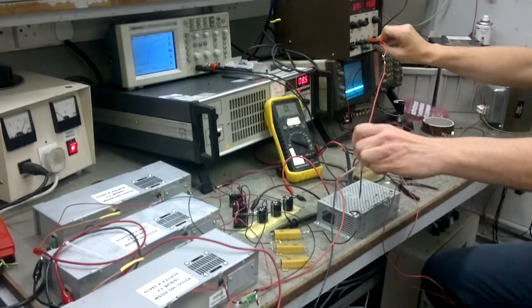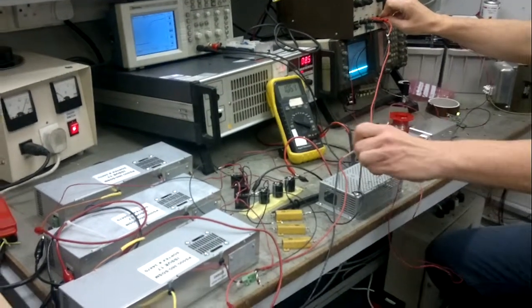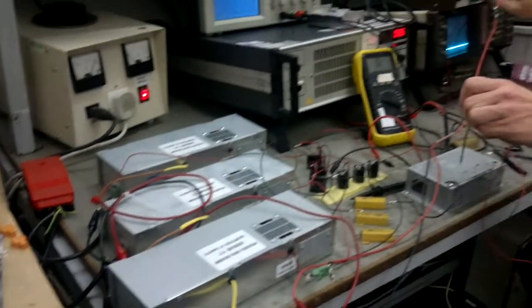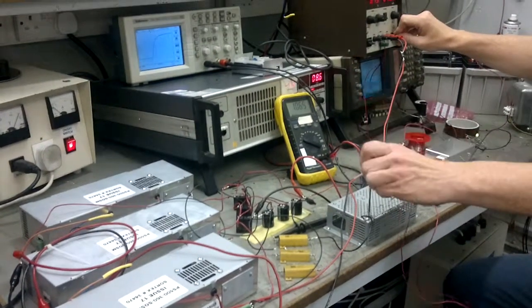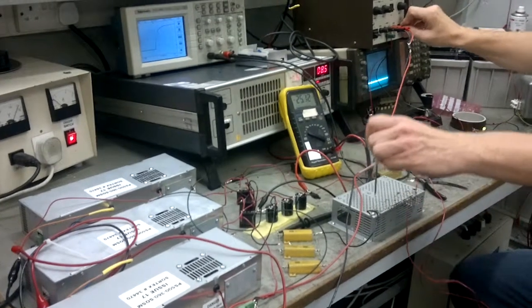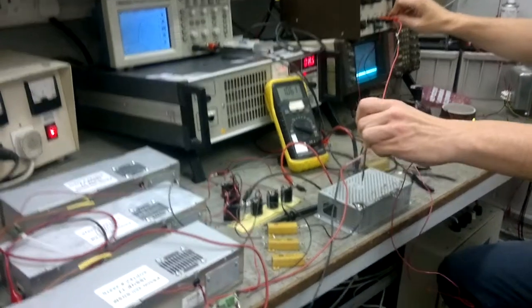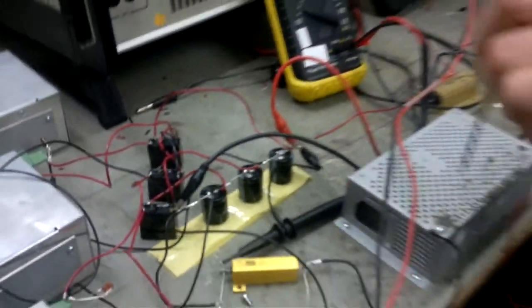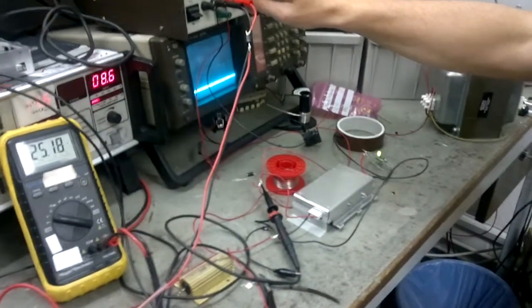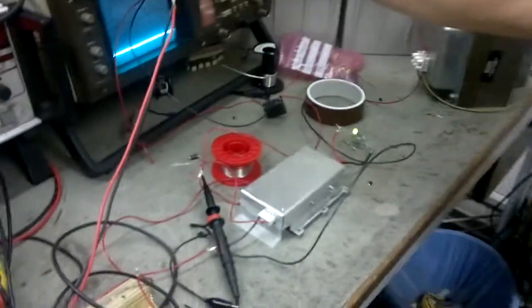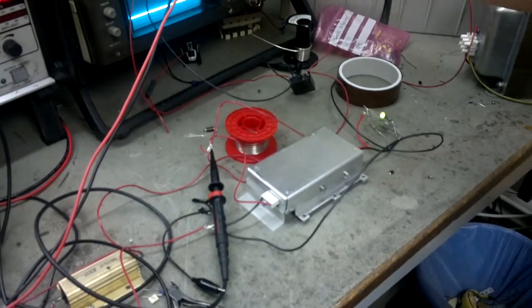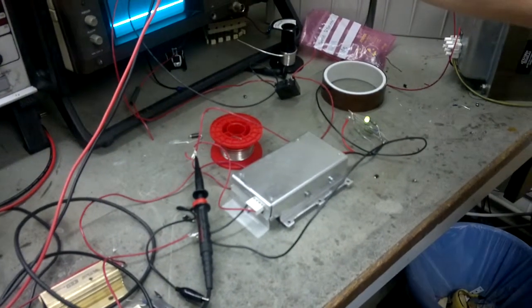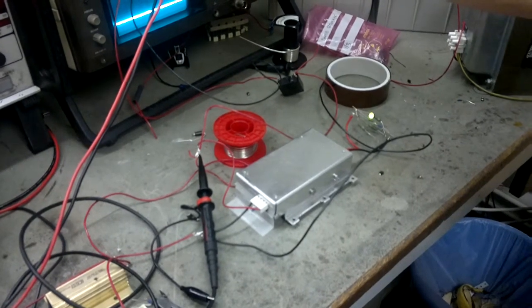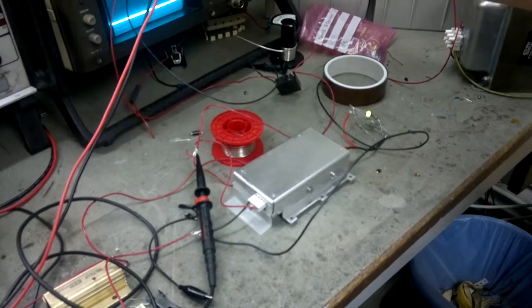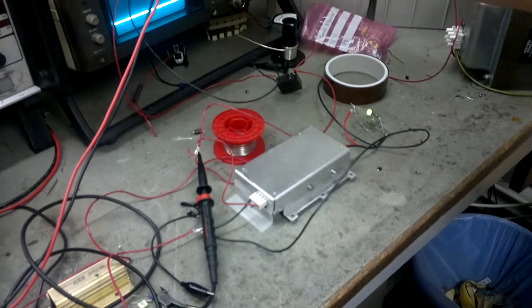Just to explain that, as we said, the 3 big power supplies here are charging the bank of capacitors, then the power supplies are switched off and the relay is open circuited, and then only the energy in the 3 capacitors here is dumped into the DC to DC. As we can see during the test, although 1100 volts negative is applied to the unit, the LED indicating the DC output voltage at 12 volts does not flicker. There's no interruption to the unit's performance.